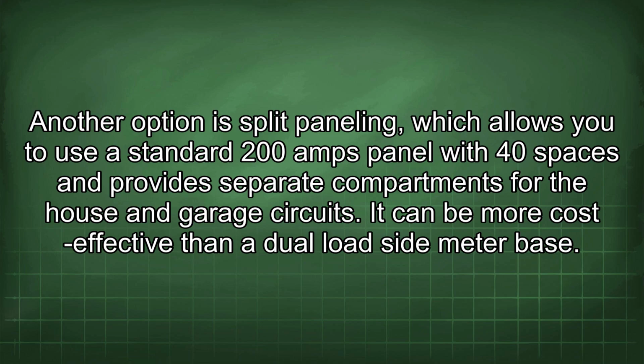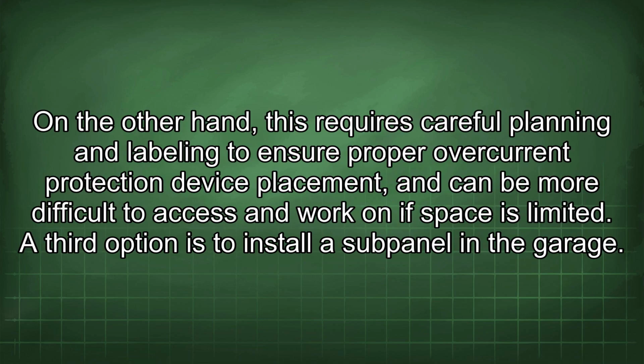Another option is split paneling, which allows you to use a standard 200 amp panel with 40 spaces and provides separate compartments for the house and garage circuits. It can be more cost effective than a dual load side meter base. On the other hand, this requires careful planning and labeling to ensure proper overcurrent protection device placement, and can be more difficult to access and work on if space is limited.